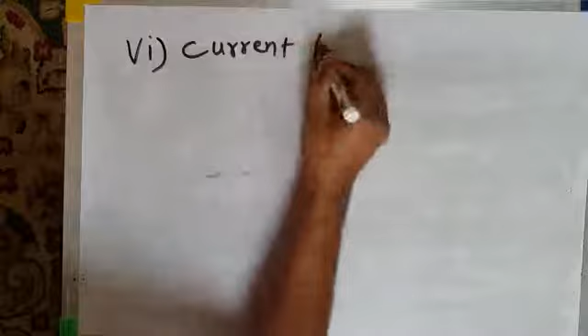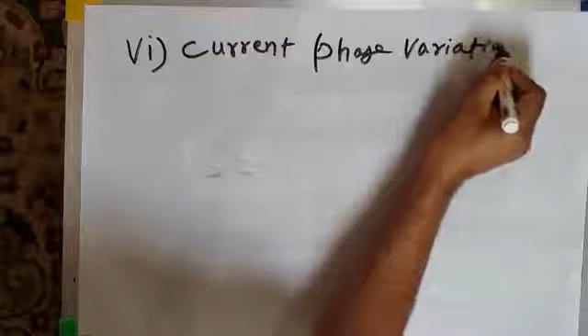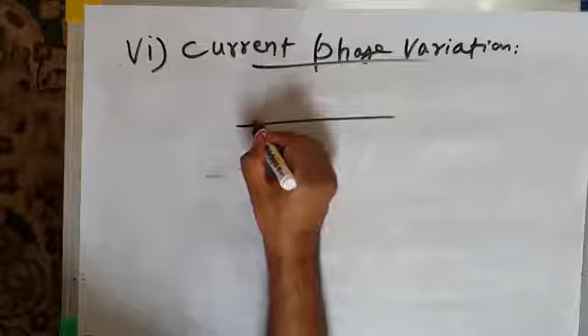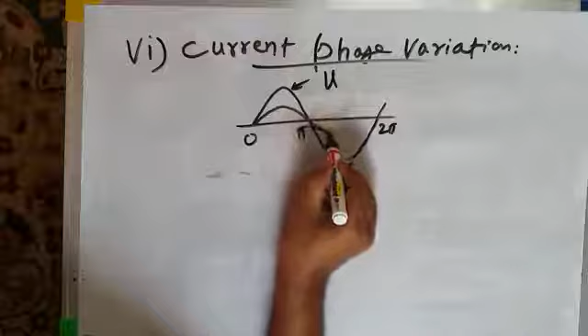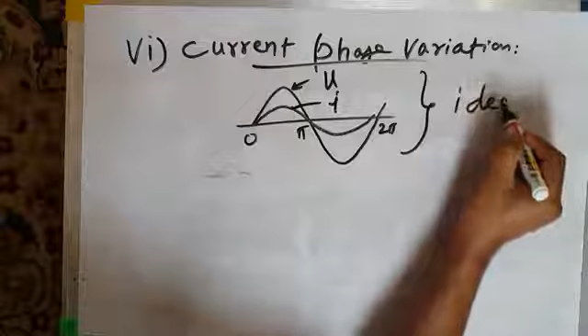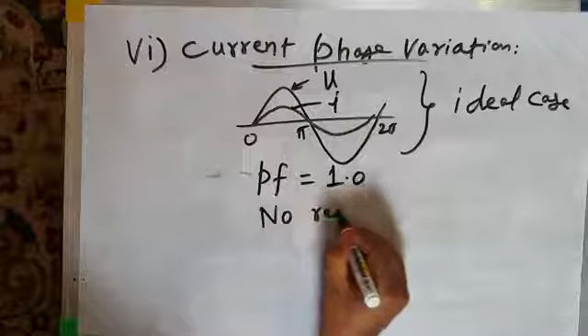Sixth is current phase variation. Ideally, what should be the phase angle between distribution voltage and current? If this is your distribution voltage V, say from 0 to pi to 2 pi, the distribution current drawn by the load should be in phase with the voltage, ideally. This is an ideal case: current in phase with the voltage. When current is absolutely in phase with the voltage, what is the power factor of the distribution system? It is unity, 1.0. And unity power factor means there is no reactive power flowing in the distribution system.